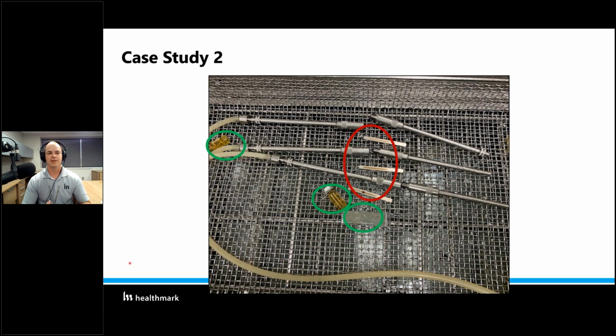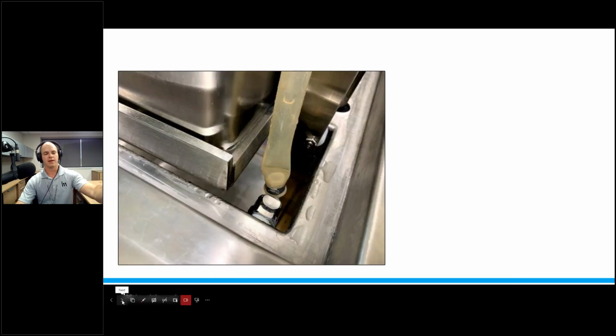Maybe it's already jumping out at you, but in case it didn't, what happened here is my friend Sharon Rojo was getting set to retest this ultrasonic cleaner after we discovered the failure. He was selecting the cycle, and it was about to lower the tray into the ultrasonic, and we noticed that this tubing kinked completely as it was submerged below the water. So that is what led to the diminished flow through that lumen cleaning functioning portion of the Sonic. It made complete sense after that why we failed our lumen cleaning test.